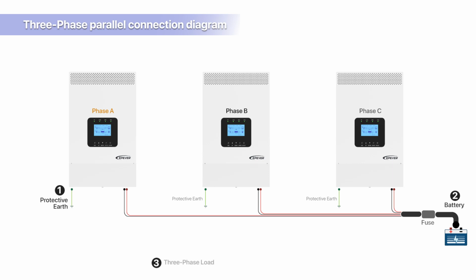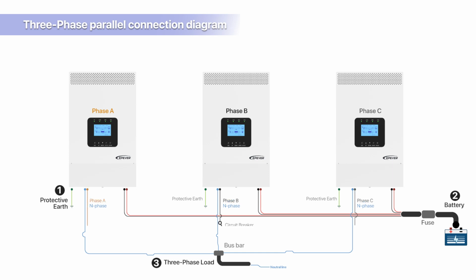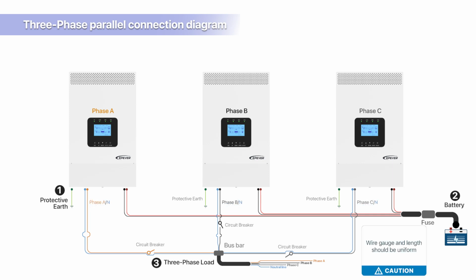Load connection. First, connect the neutral wire, N phase, of all devices separately to a bus bar, then connect this bus bar to the load. Next, connect the live wire of each device to the corresponding A, B, C phase on the load, as per the A, B, C sequence settings. The wire gauge and length for each inverter's connection to the AC load should be the same.